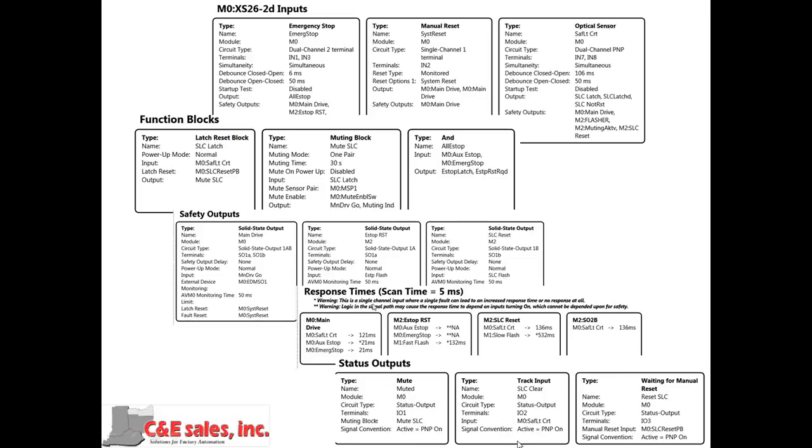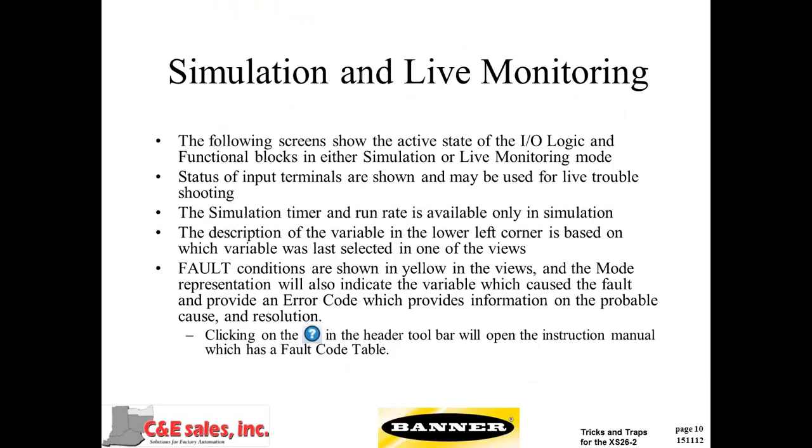You may remember that there are a number of terminals called I/O terminals, which can be used in 3 different modes: either as ordinary inputs, as pulsed outputs for dry contacts if you need a category 4 PLE where you need to look for wire-to-wire short, or you can map them as non-safety outputs as monitors.